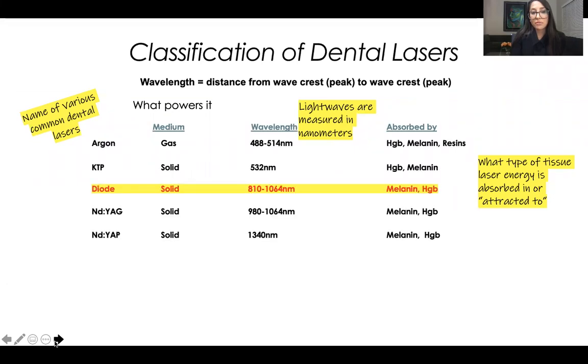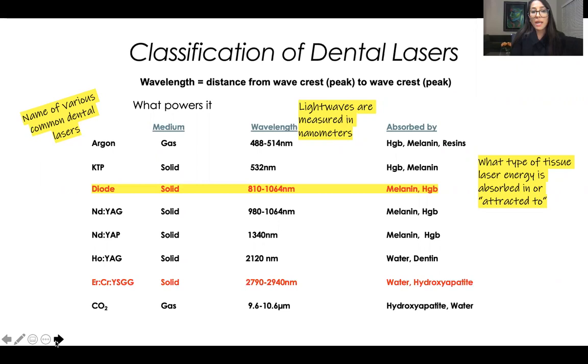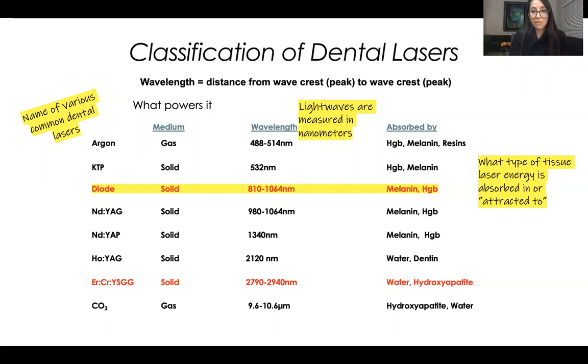When we look at the classification of lasers, we go by their name, common name, what powers them, their range or family, and their category of wavelengths. Diode lasers operate on a solid active medium. Their wavelengths measure from 810 to 1064 nanometers, and they're attracted to melanins and hemoglobins — best absorbed in tissue that contains melanin and hemoglobin. The bottom-listed lasers are hard-tissue or all-tissue lasers, because the light absorbs best in hard tissue.